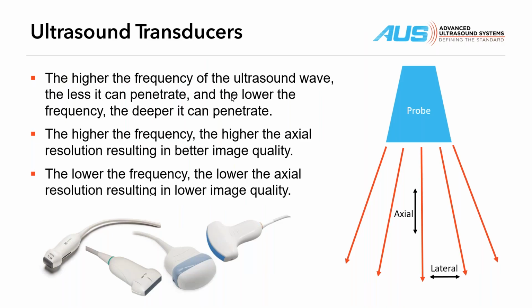So everything in ultrasound, as far as probes go, is with a sacrifice. Either you're sacrificing penetration to get better resolution, or you're sacrificing resolution to get more penetration. And it's crucial for you to know that and to recognize that while you're troubleshooting image quality issues. Is it a real problem, or is it because they're using a different probe, perhaps a different frequency setting? It's important for you to understand the relationship that frequency has on image quality. So it's kind of a pillar of ultrasound.